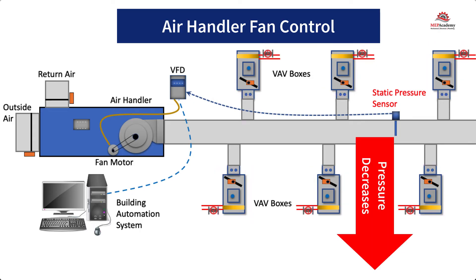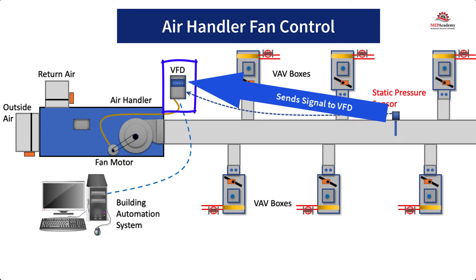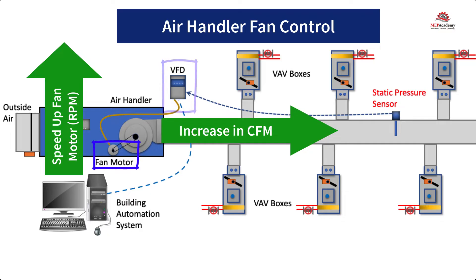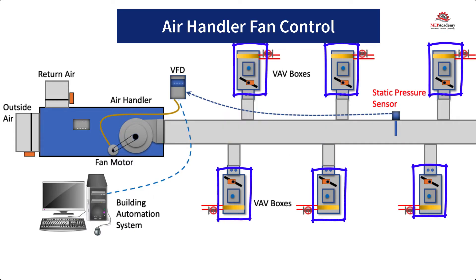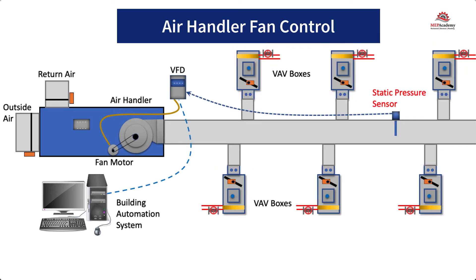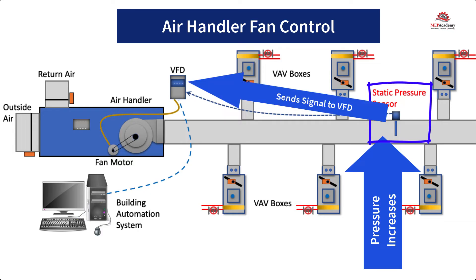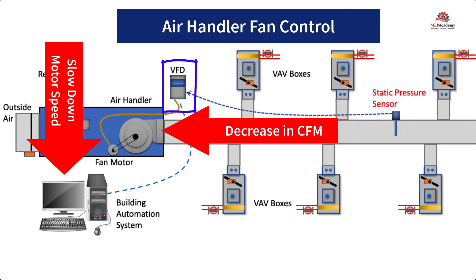As the variable air volume boxes begin to open their dampers because of an increase in cooling demand, the pressure in the supply duct drops. When the pressure in the supply air duct decreases, the static pressure sensor sends a signal to the variable frequency drive to increase the speed, the RPM, of the fan motor, causing an increase in CFM. The opposite happens when the VAV box dampers begin to close because the spaces are cold enough. As the dampers begin to close, the pressure in the supply air duct increases, causing the static pressure sensor to send a signal to the VFD to slow down the motor of the fan, reducing the amount of CFM.